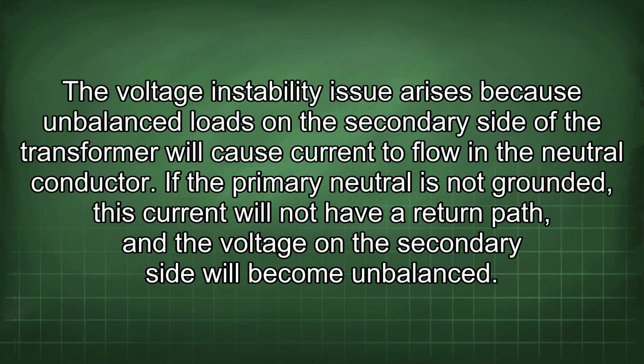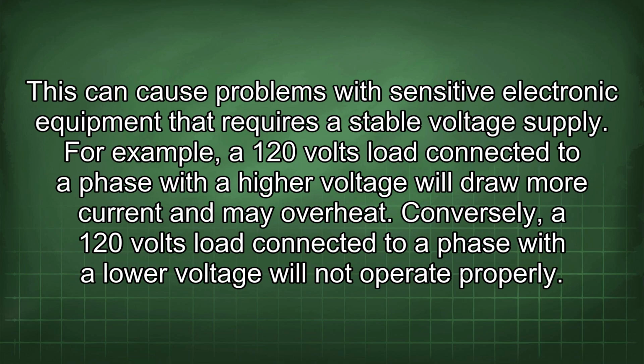The voltage instability issue arises because unbalanced loads on the secondary side of the transformer will cause current to flow in the neutral conductor. If the primary neutral is not grounded, this current will not have a return path, and the voltage on the secondary side will become unbalanced. This can cause problems with sensitive electronic equipment that requires a stable voltage supply. For example, a 120 volts load connected to a phase with a higher voltage will draw more current and may overheat. Conversely, a 120 volts load connected to a phase with a lower voltage will not operate properly.